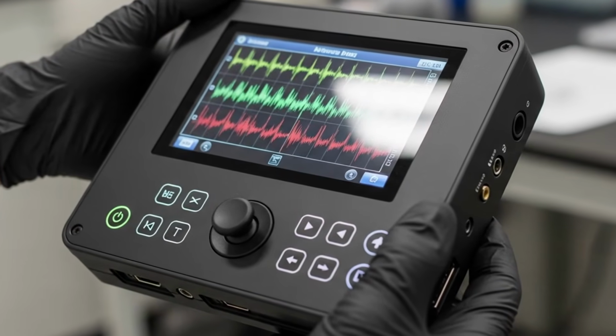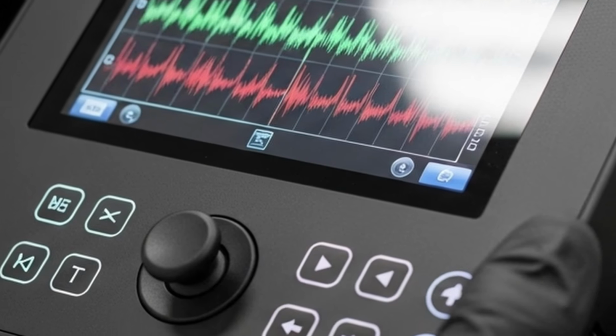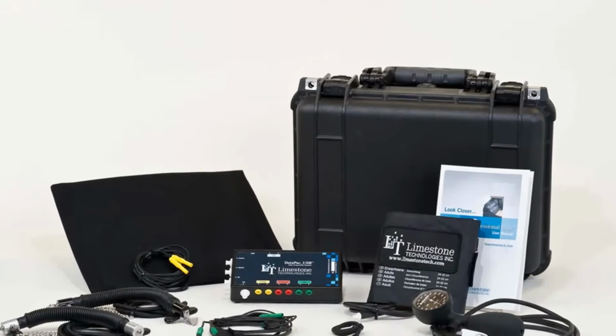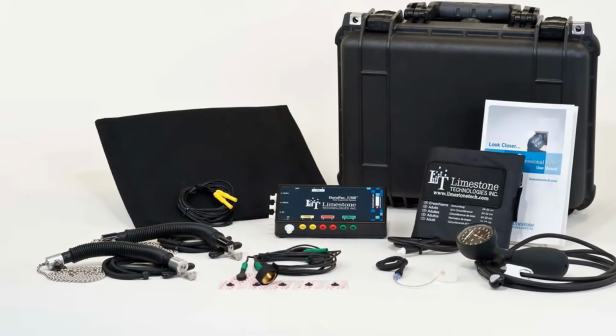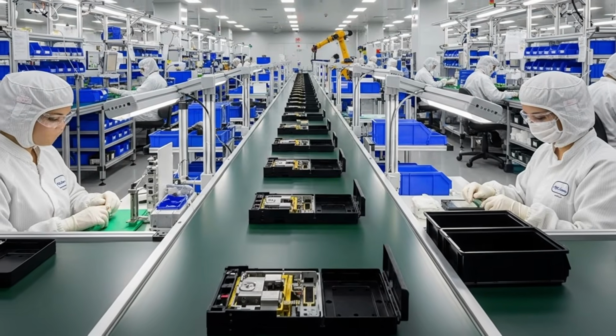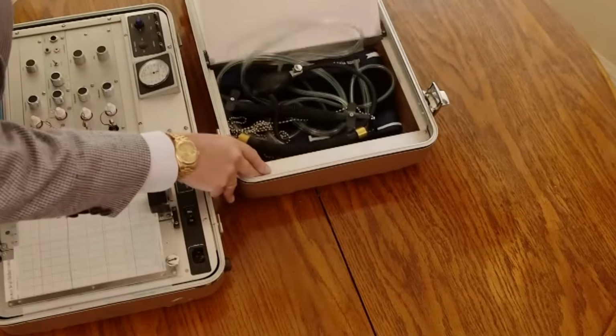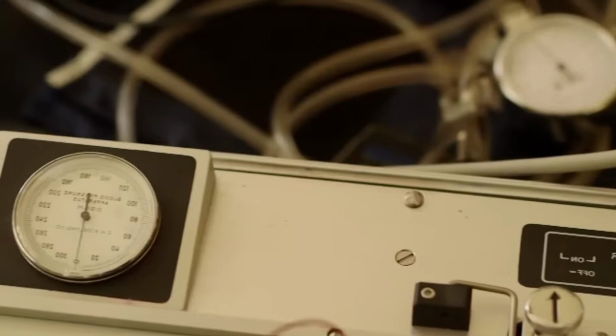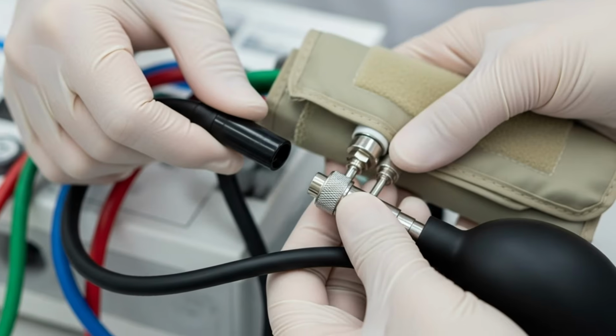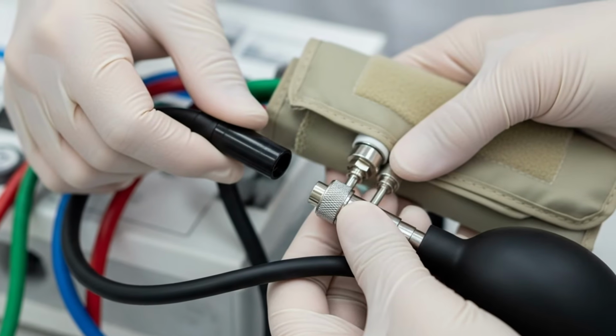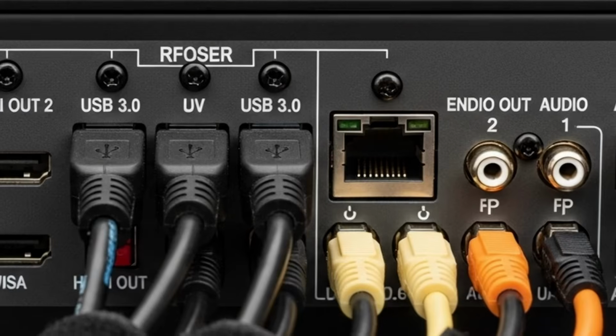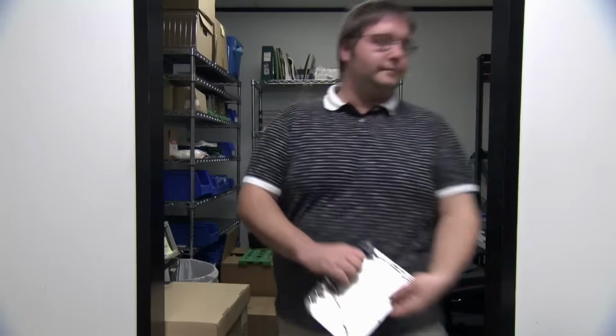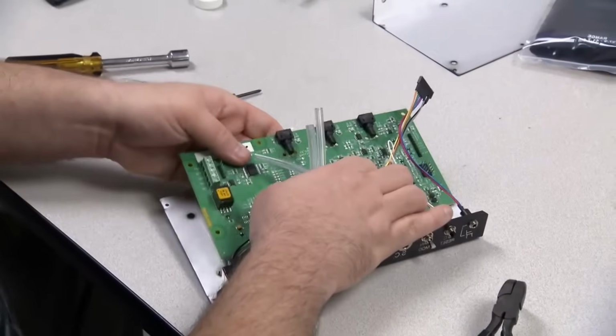The pneumographs, blood pressure cuff, and electrodes are connected to the central unit using color-coded medical-grade connectors, ensuring secure attachment with no signal loss. The central unit is fitted inside the housing and secured with titanium screws, chosen for their resistance to vibration and corrosion. Then, the control software is uploaded through a USB port, configuring the system to interpret physiological signals in real time. In some models, built-in artificial intelligence algorithms automatically adjust analysis parameters to improve accuracy.